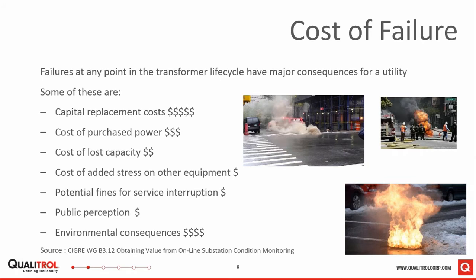Maybe you have additional routes for the power, so there's no cost of lost capacity generally with voltage transformers. Those costs are more associated with large transmission transformers or even GSUs. And there's no cost of purchased power, but there is going to be additional stress on other equipment as power is rerouted, and that will have some cost because it will result in some level of increased aging of that equipment. If it's a building or business with a supply contract and the power goes out, there might be fines for service interruption. This is quite common in some parts of the world.